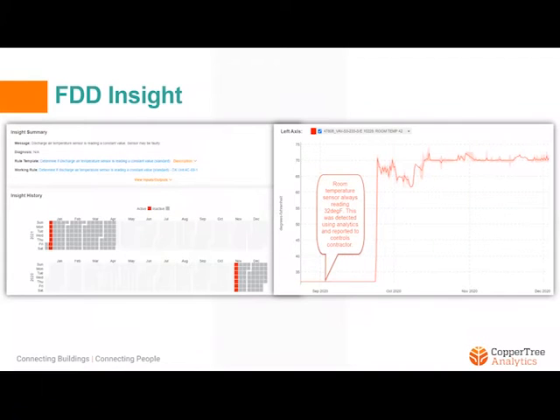FDD Insights. So let's say the rule has been implemented. What is next? Well, the rule goes to work for you, and it generates insights or alerts or notifications whenever something of interest happens in the building. On the left-hand side, you're looking at an insight summary. The message says, discharge air temperature sensor is reading a constant value. Sensor may be faulty. What I really like here is the insight history, which is a newly added feature.